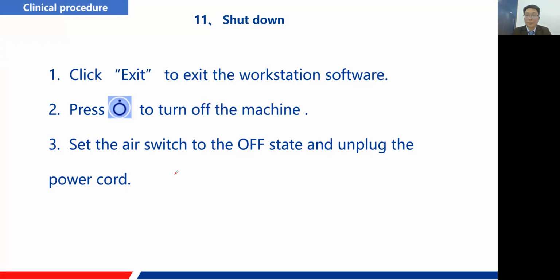Next one is shutdown. We can only press the power off to turn off the whole machine. Before that, we need to exit the workstation software, and then press the power off button to turn off the whole machine. The computer and the UPS power supply will turn off automatically. After the computer is turned off, see that its indicator is off, and also look at the UPS power supply indicator. After this, set the air switch to the off state and unplug the power cord.